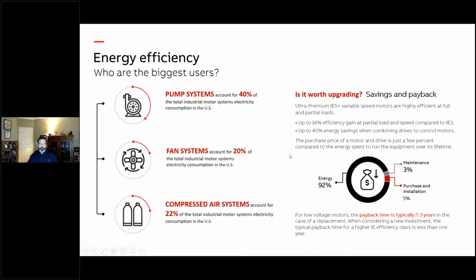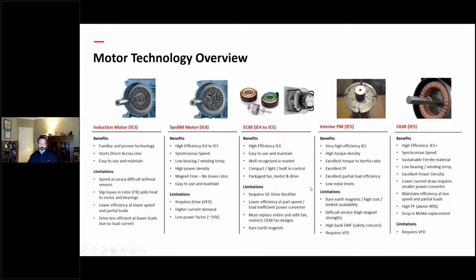And that's where you really get these big paybacks. So I'm going to actually show you real world test results at the partial load conditions. But instead of a couple points of efficiency difference, you're going to see with the technology much higher efficiency differentials, up to 16%, because this motor design gives you more flat efficiency performance when you're running at slower speeds and at partial loads.